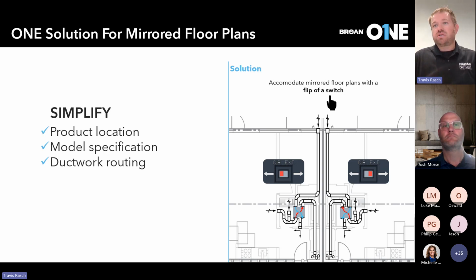Ductwork routing, so you saw how ugly the previous one was. Now we got this nice clean ductwork on this particular plan here, and that's all again made possible by the fact that the unit's physically installed in the same location. We're simply making that choice in the field as to what side of the ERV the exterior ductwork is running to.